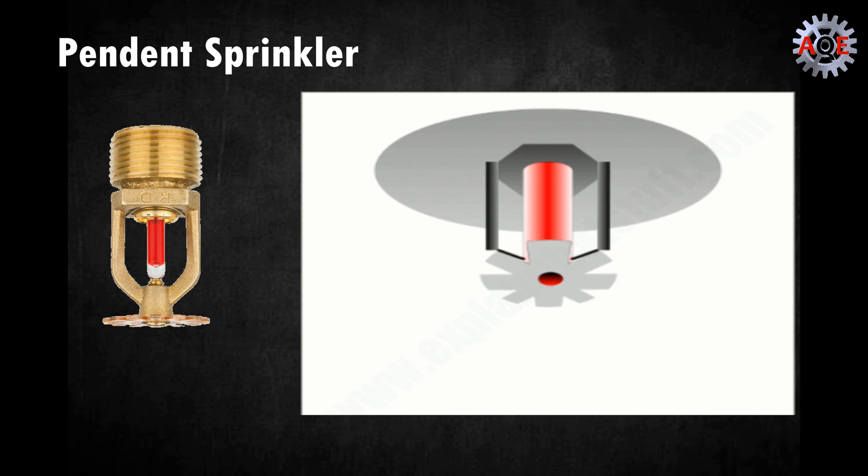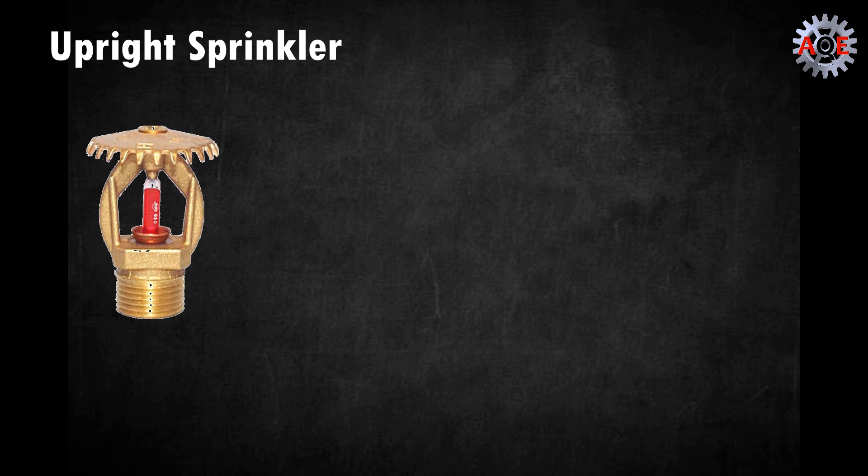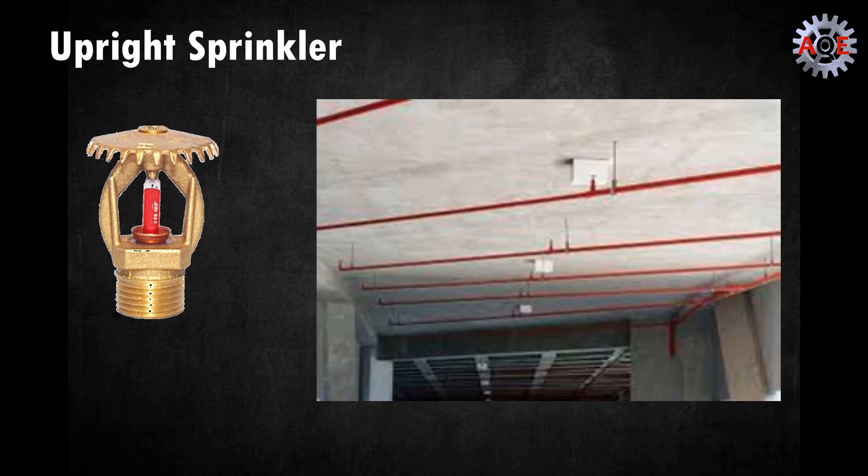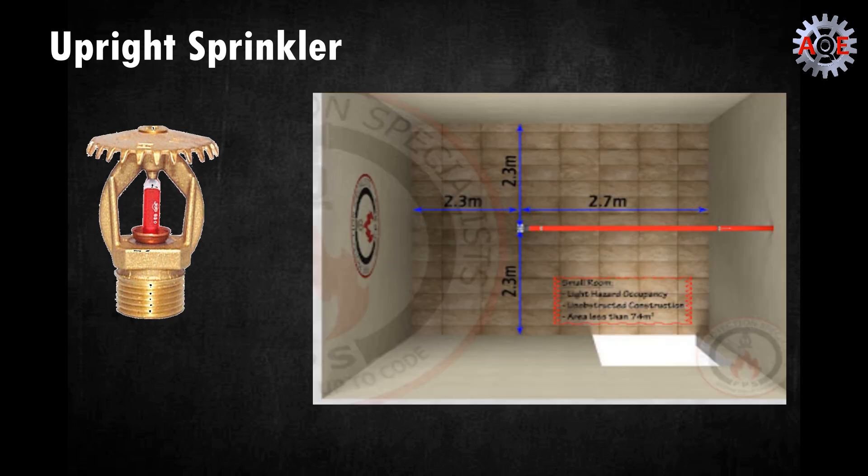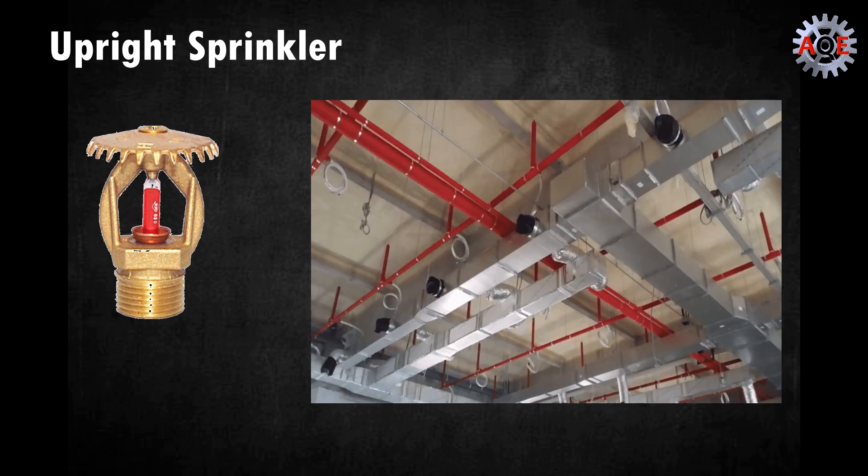An upright fire sprinkler points upwards towards the ceiling. The deflectors are also curved down so that the water sprays in a hemispherical position. They're generally used in mechanical rooms or rooms that are difficult to access. They also offer great coverage for obstructions such as air ducts.